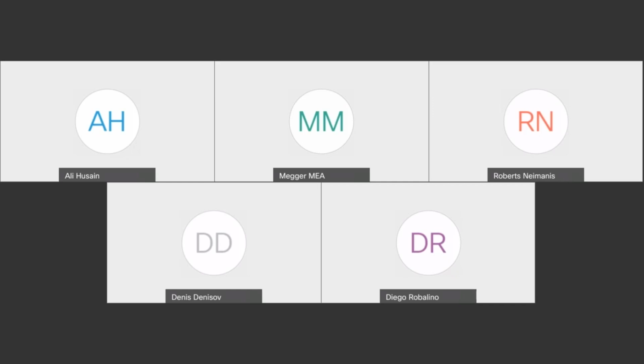The other thing is that, especially because of the bottom envelope or the bottom part of your bushing, it's immersed in oil, or it has the connections, and could be shielded. There are so many different constructions, and that's the reason why when we were talking about the analysis based on C2, I did mention that you can take, for example, an OIP bushing and do the testing outside of the transformer. But when you install that bushing in the transformer and you put that already in oil, you will see that there might be a difference in your C2 value.